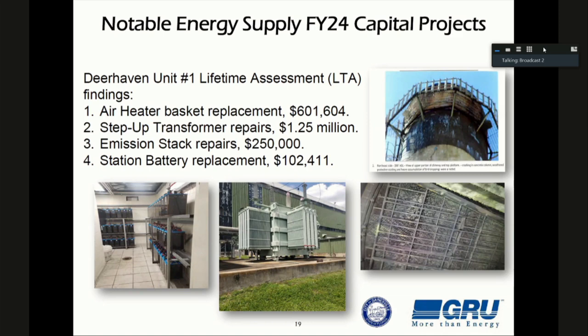The last item is all of our control systems require a DC backup, a direct current backup. So we have a battery associated with the plant - these are station batteries, you see it in the far left-hand corner. That station battery is rated by its capacity - once it's discharged, what capacity is left of the unit. We do that test every year, and 80% is the low end; you can't go beyond that.